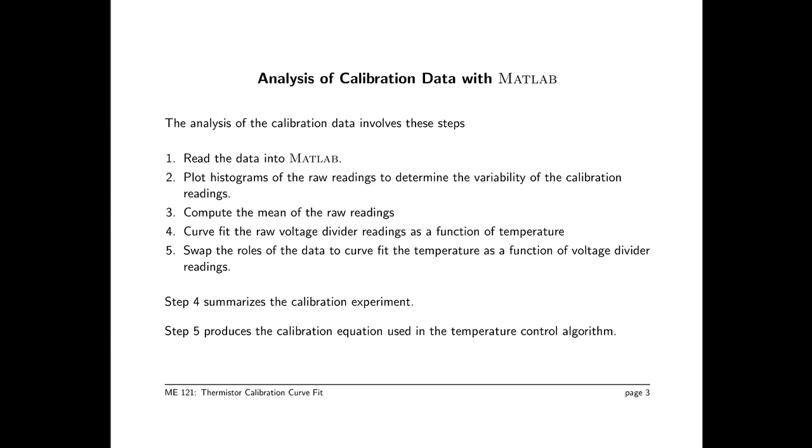The calibration data reduction follows these steps. You read the data from the previous slide into MATLAB. To investigate the quality of that data, you're going to plot histograms for each reading, each temperature setting of the calibration experiment. Inspecting the histograms allows you to determine that the data is good. And then you can compute the mean of each column of raw readings. And then the question is how to convert that into a function. Step four describes making a curve fit of voltage as a function of temperature. Step five is useful because that produces a function that you can use in your temperature control algorithm.